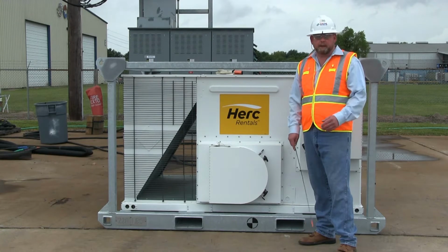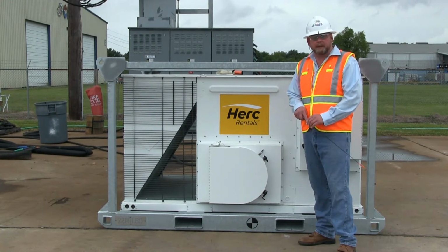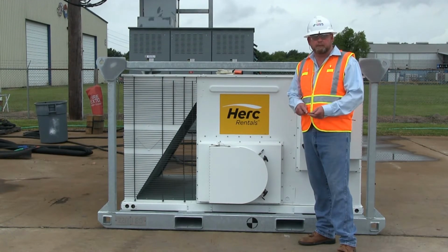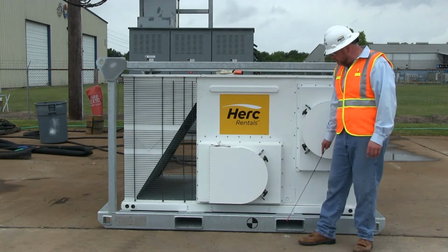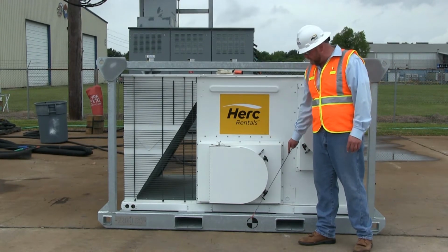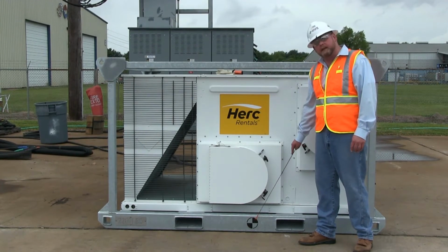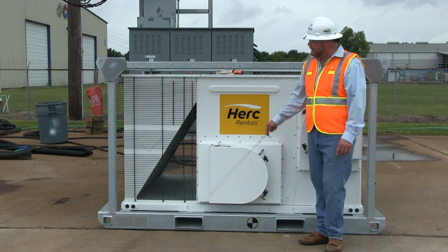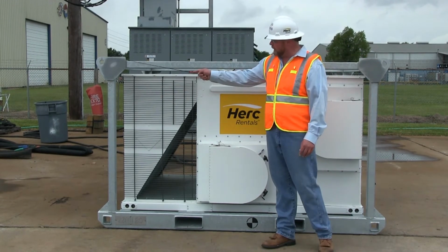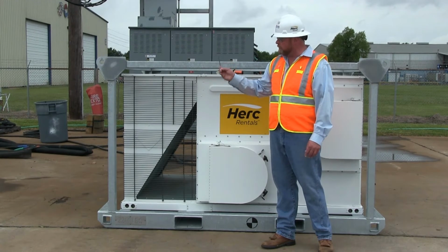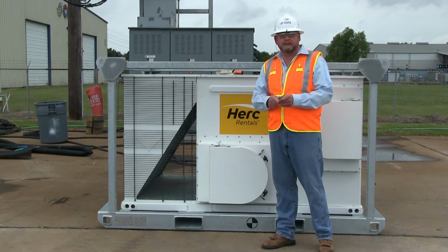The first step in installing the 10-ton package unit is to determine how it's going to be transported. We have a set of forklift pockets here at the base of the skid with the center of gravity clearly marked. Additionally, we have overhead lifting provisions for all four corners. This is a certified lifting stacking cage.